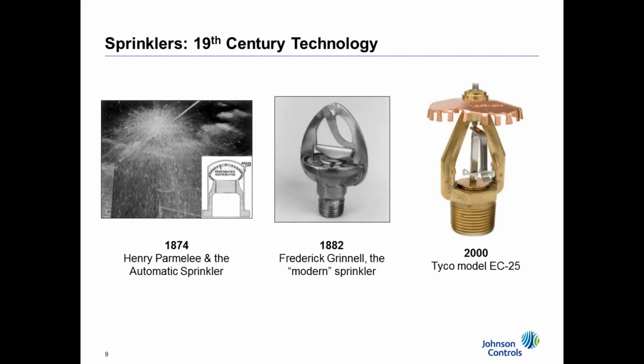Again, a quick history for those who may not be aware. Henry Parmalee actually developed the first automatic sprinkler in 1874. But it wasn't until 1882 when Frederick Grinnell actually modernized what we call today's sprinklers. It was a solder seat linked in place. And if you look to the far right-hand side, that is a 2000 model of the Tyco extended coverage 25 orifice. It's a 1-inch thread. It's used in storage applications. But in all these cases, you're relying on thermal activity of those elements to operate.